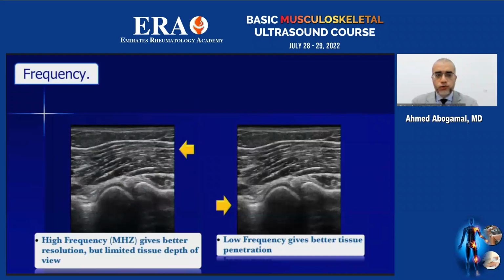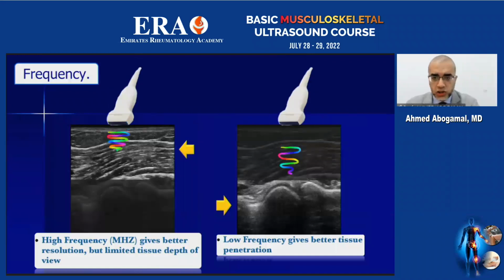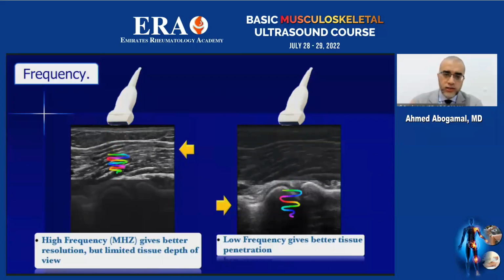Regarding frequency, it is very important to memorize that with higher frequency, there is lower penetration of the ultrasound waves. That's why if you're going to examine a deeper structure, you have to rely on low frequency ultrasound waves to have good penetration. But with good penetration and lower frequency, you have a lower resolution, as resolution is always connected to higher frequency. So if you're going to examine a superficial structure, please rely on high frequency ultrasound waves. And if you're going to examine a deeper structure, you have to utilize lower frequencies.